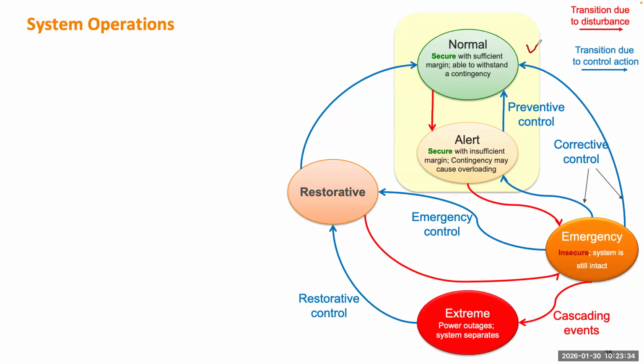For instance, maybe the system has two areas, and one area sends power to the other area, but there are many transmission lines. So even if you open one line, which is considered an N-1 contingency, the remaining lines have enough margin to deliver the power. So the system is very secure. That is considered the normal condition, which is the green bubble.